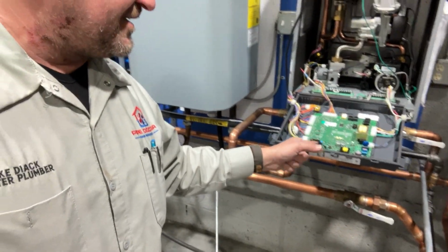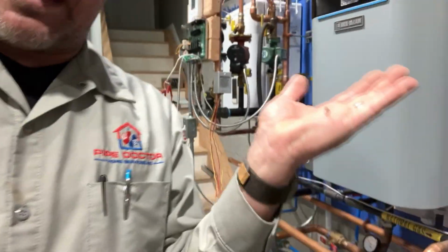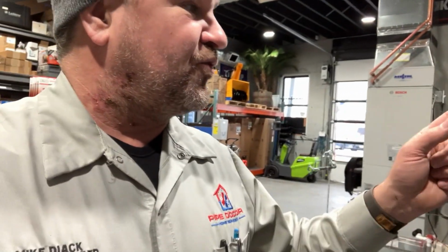In this installation, it's not even a day later. Hypothetically, something wrong with the control board killed the fuse going to there. Now, if there were more problems with this, or if we saw a problem with this, obviously something wrong with the control, it's a lot more than a fuse, but nonetheless, we're going to replace that switching relay with a new one. So, step by step, let's get it done.